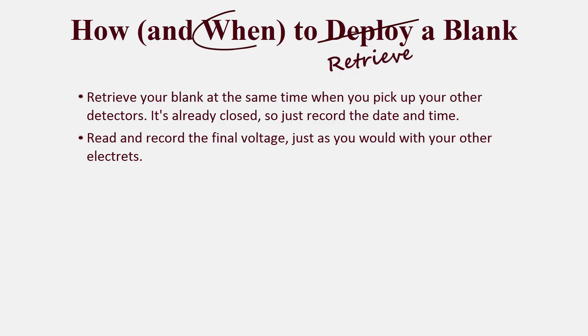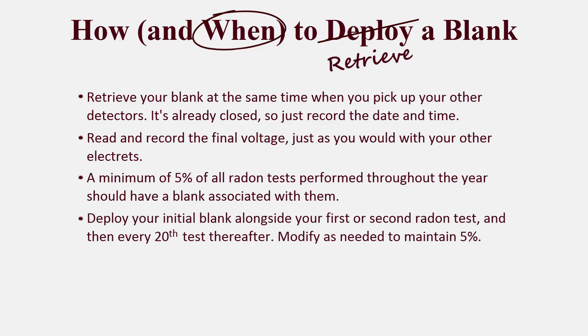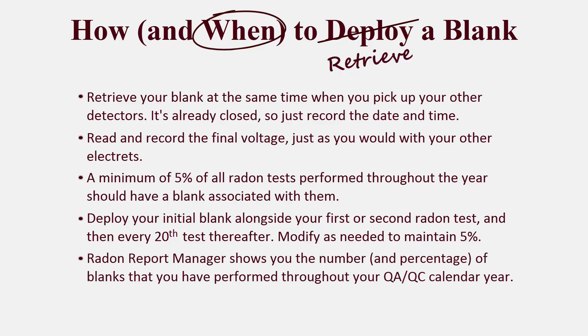Let's talk about when we should deploy a blank. In order to comply with standard QAQC practices, a minimum of 5% of all radon tests performed throughout the year should have a blank associated with them. This means that you should start off your first or second test with a blank and then deploy another blank every 20th test thereafter. The Radon Report Manager will show you the number and percentage of blanks that you've performed throughout your QAQC calendar year.